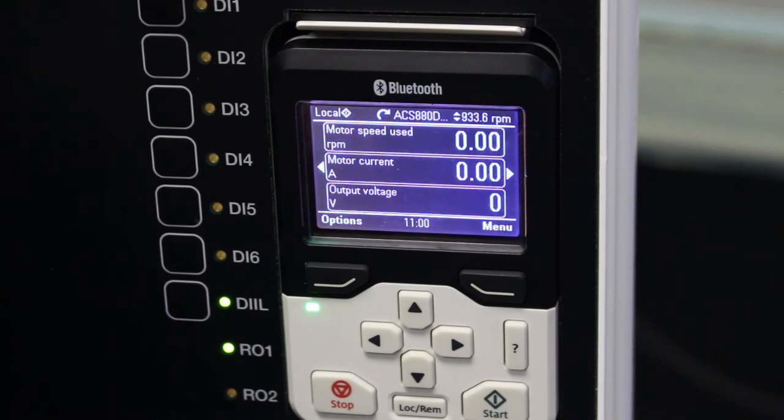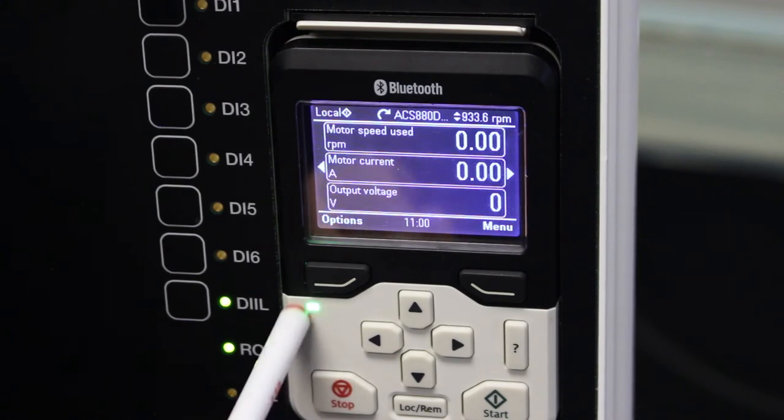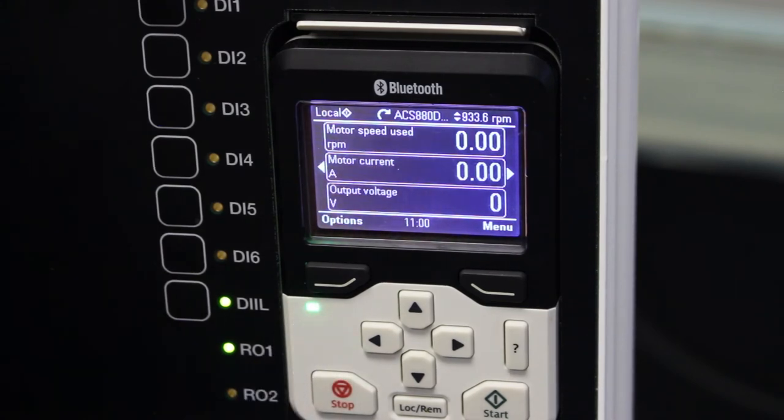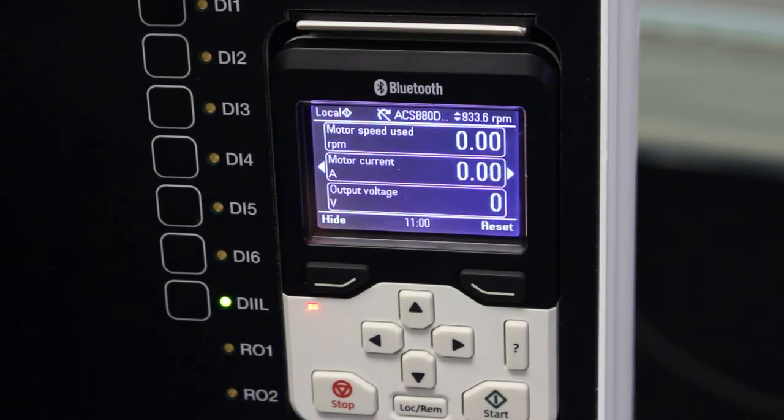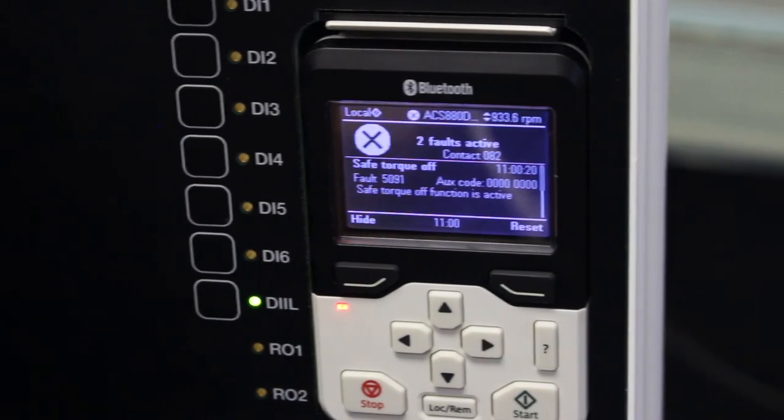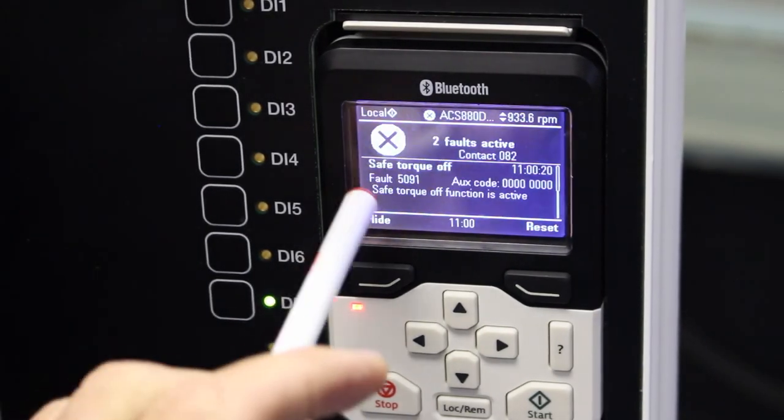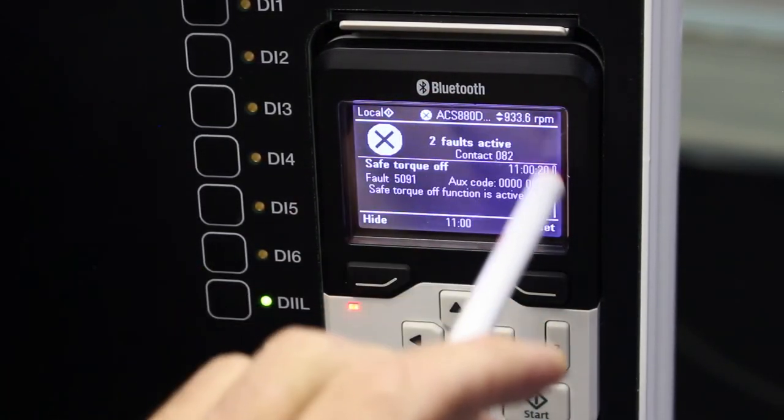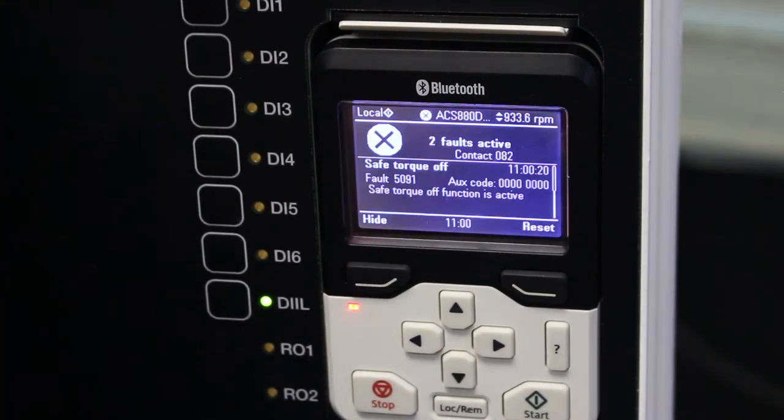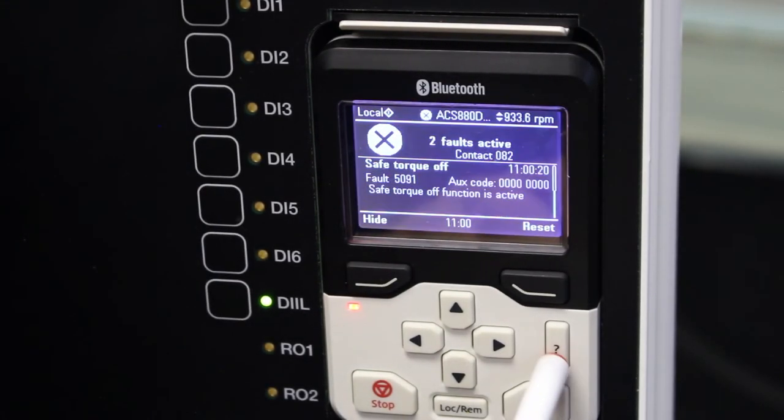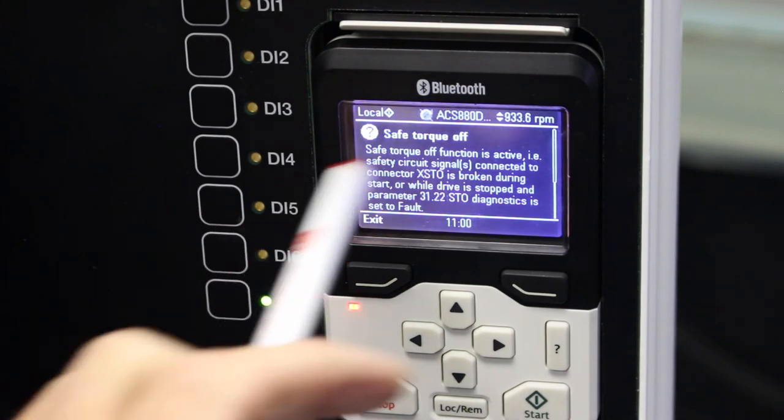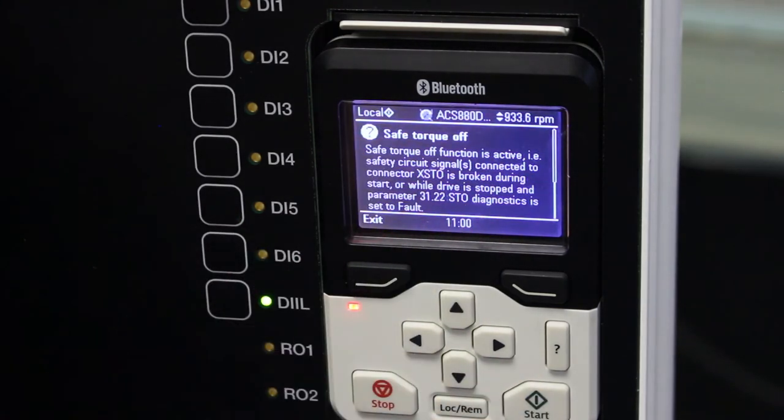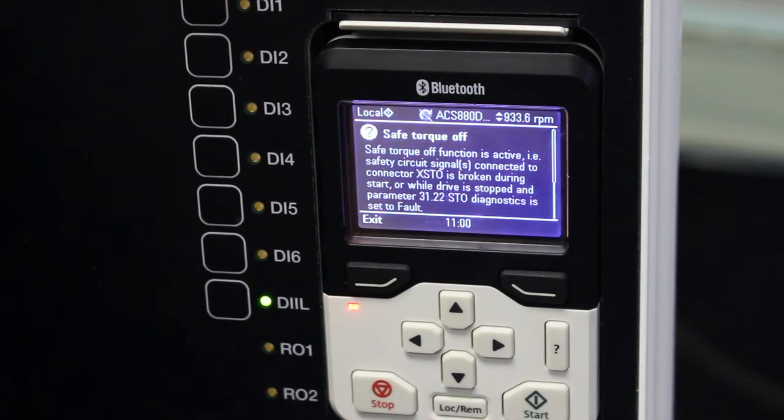If I have an alarm, that alarm light, this light will flash green. If I've got a fault, a trip for instance that I've created now, it will turn into red and it will show me over here what the fault is. I can press this little question mark over here and it will give me some more information about what the fault is.